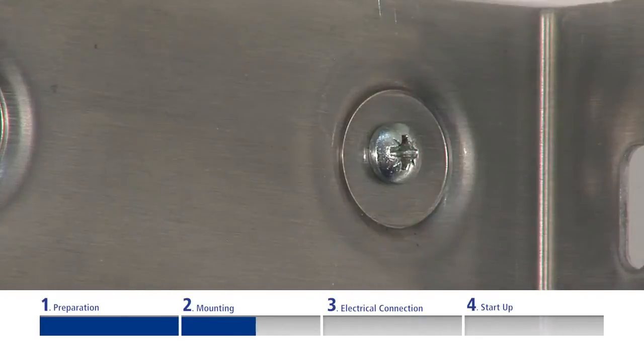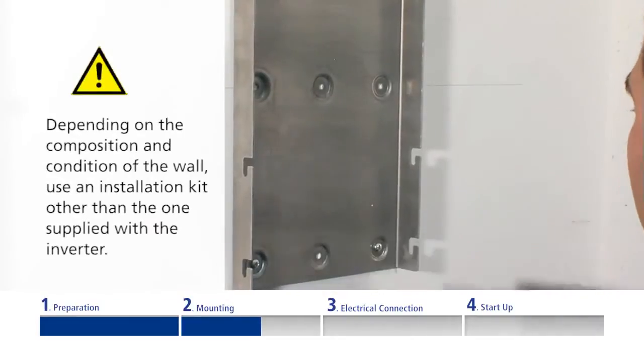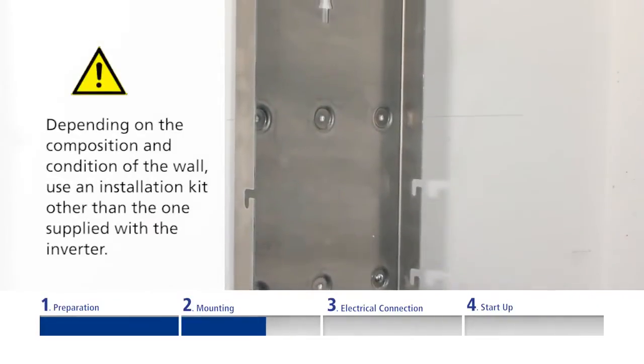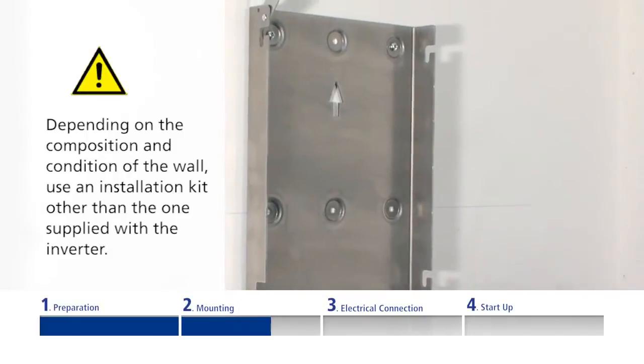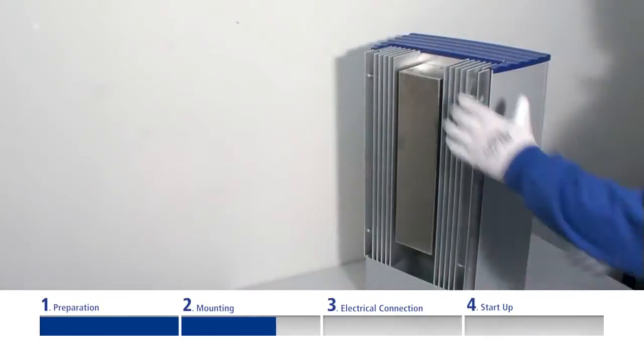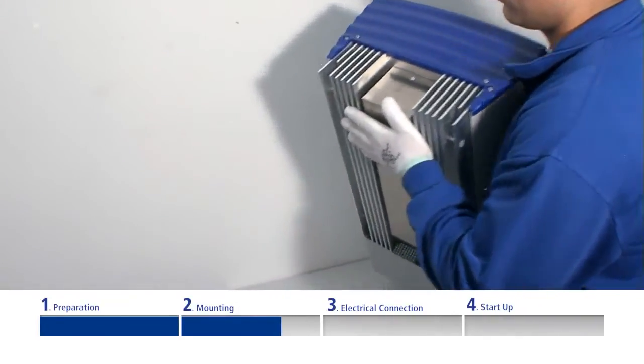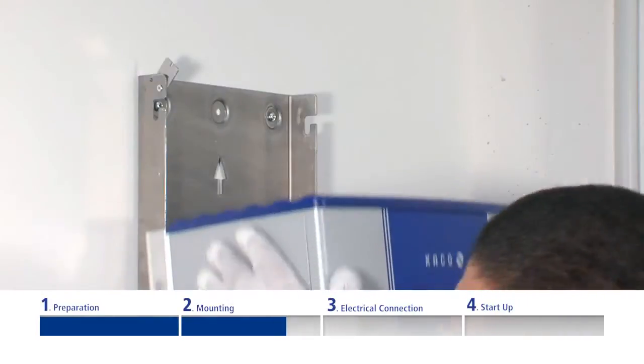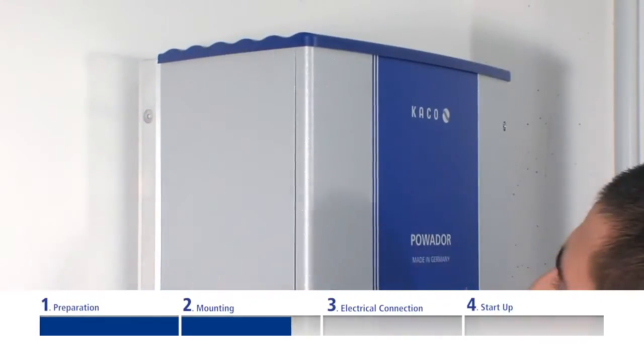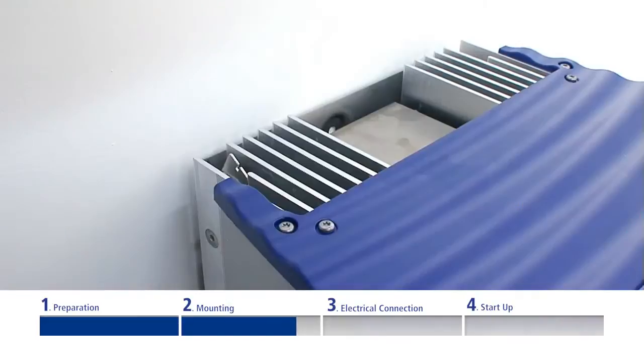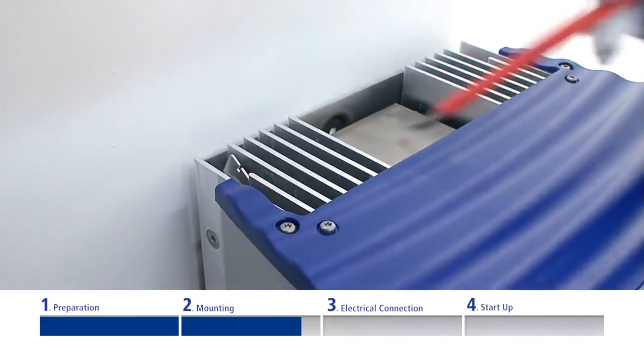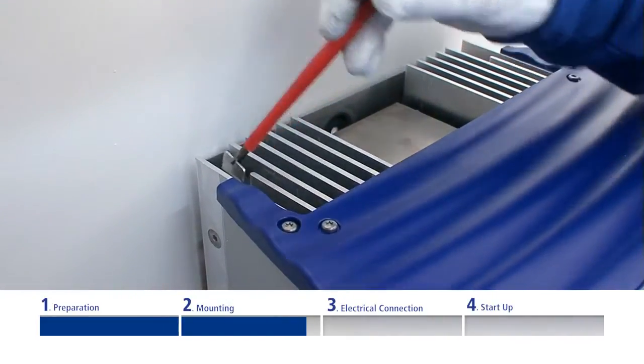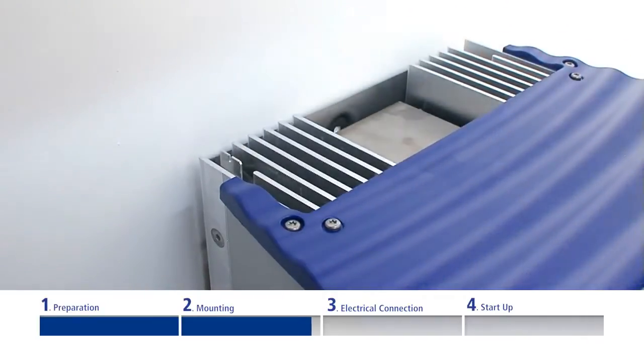If necessary, depending on the composition and condition of the wall, use a different installation kit. Mount the inverter on the mounting bracket so that the pegs in the heatsink rest in the notches. Finally, lock the safety catch. To do this, slide the upper end of the catch towards the wall until the groove runs parallel to the wall.